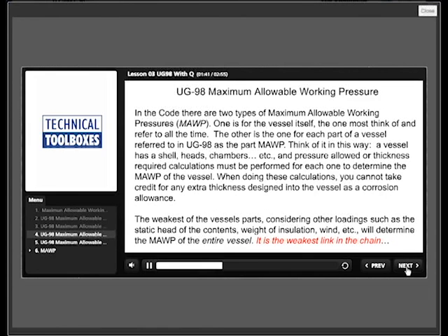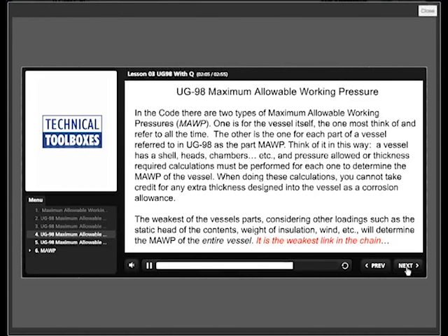Think of it in this way. A vessel has shell, heads, chambers, etc., and pressure allowed or thickness required calculations must be performed for each one to determine the MAWP of the vessel. When doing these calculations, you cannot take credit for any extra thickness designed into the vessel as a corrosion allowance. The weakest of the vessel parts, considering other loadings such as static head of contents, weight of insulation, wind, etc., will determine the MAWP of the entire vessel. It is the weakest link in the chain that determines MAWP.